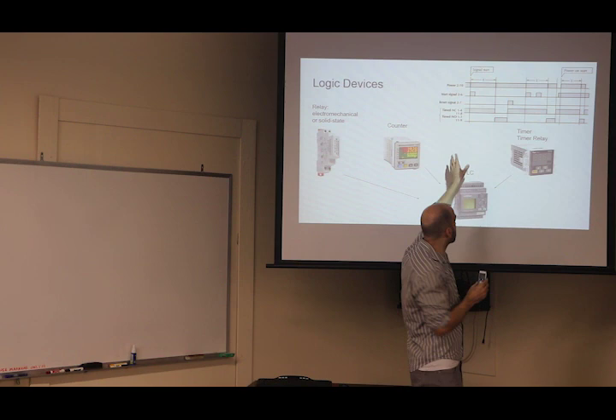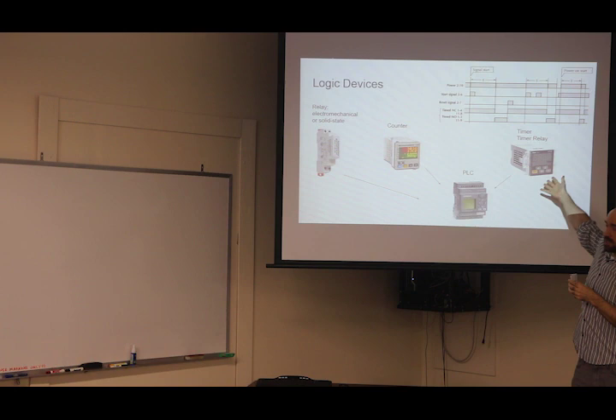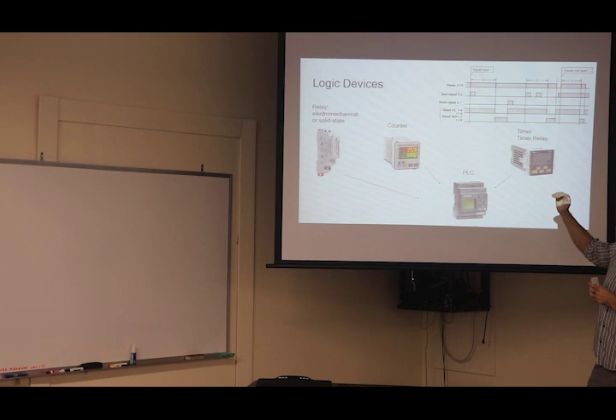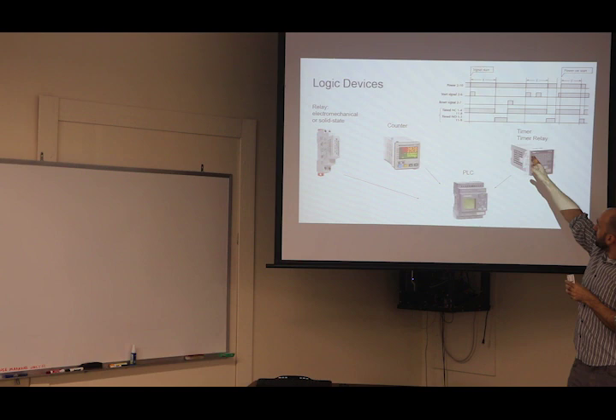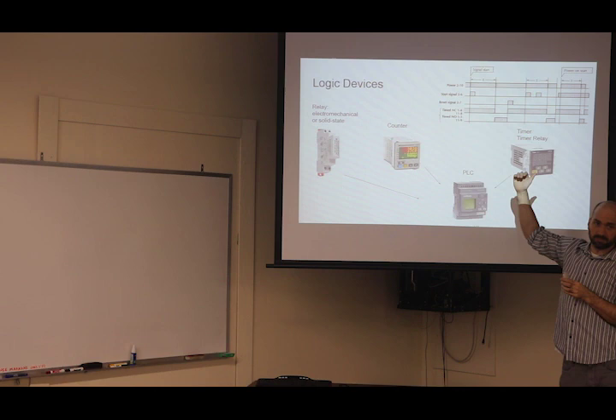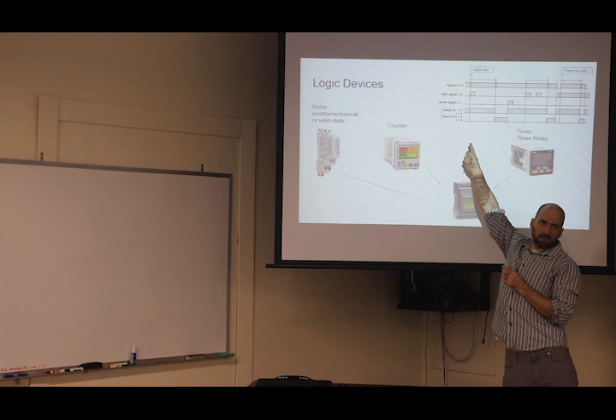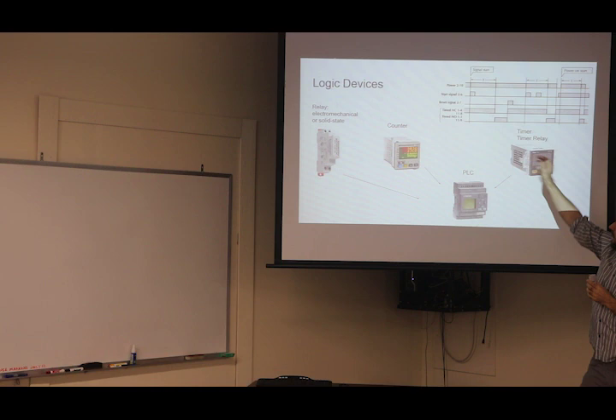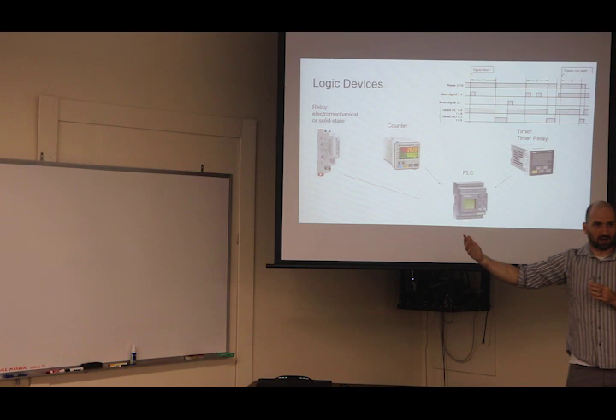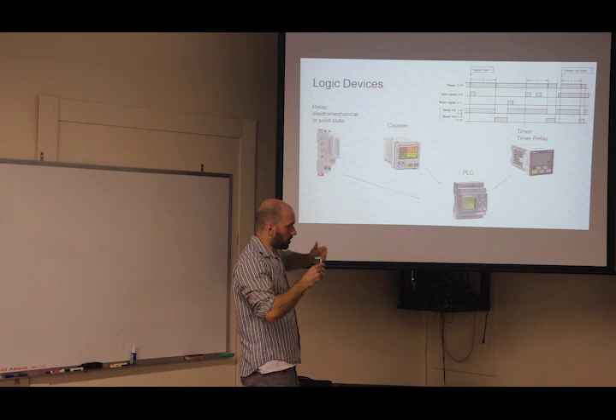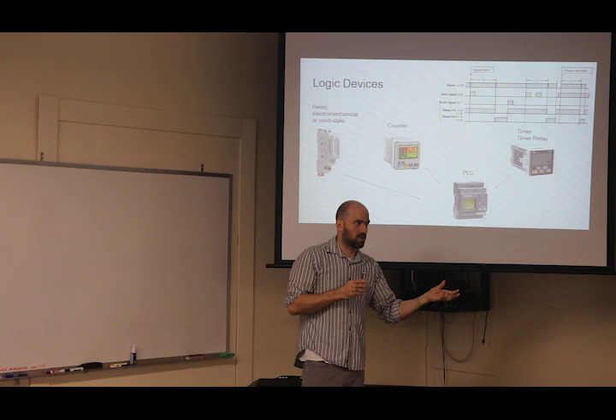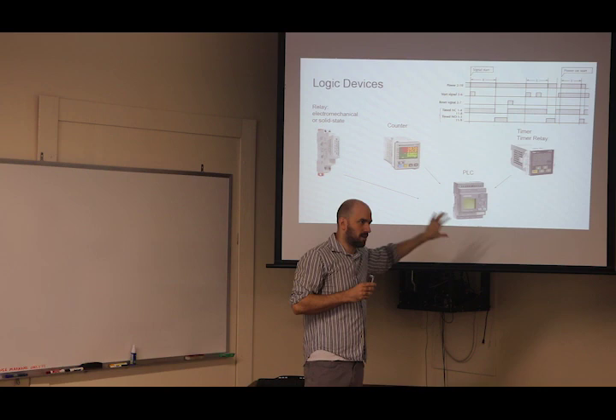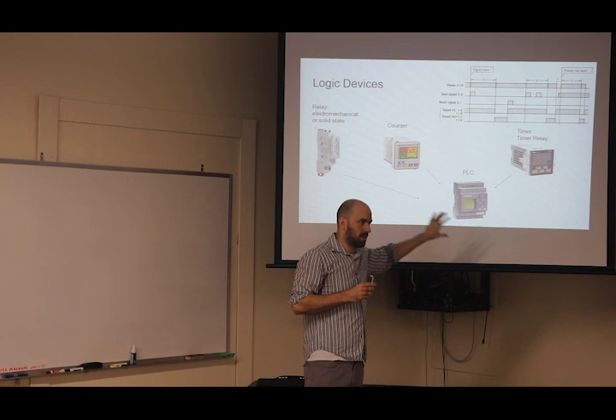Timers do what you might imagine. Power is just this thing being on or off. So the important thing to look at here is start signal, that second row. When the start signal goes, a time later your normally open channel is going to go high. So that's a normally open, normally closed. They start out like this, when this thing is just unpowered sitting on a shelf somewhere. This is how the switches are, high and low. After you send the start signal, it reverses. So that's what a timer is, is just waiting a while and then doing something else. And it used to be that people would take relays, build up all this logic, like if this relay is closed and this relay is closed then start the timer. After the timer completes, close this other relay. They would just build that with devices like this. Nowadays, it's all brought into the PLC ladder logic achieving the same thing.